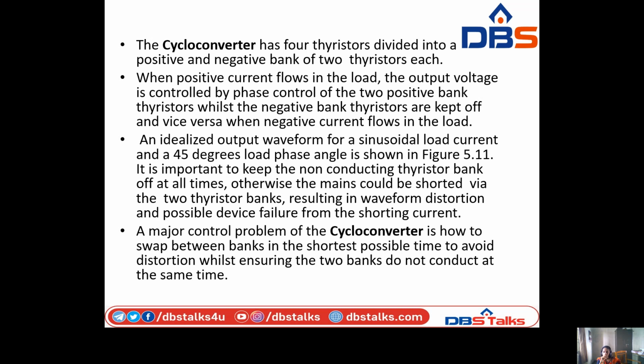The idealized output waveforms for a sinusoidal load current and a 45 degree load phase angle are shown in the figure. It is important to keep the non-conducting thyristor bank off at all times. Otherwise, the mains could be shorted via the two thyristor banks, resulting in waveform distortion and possible device failure from the shorting current.